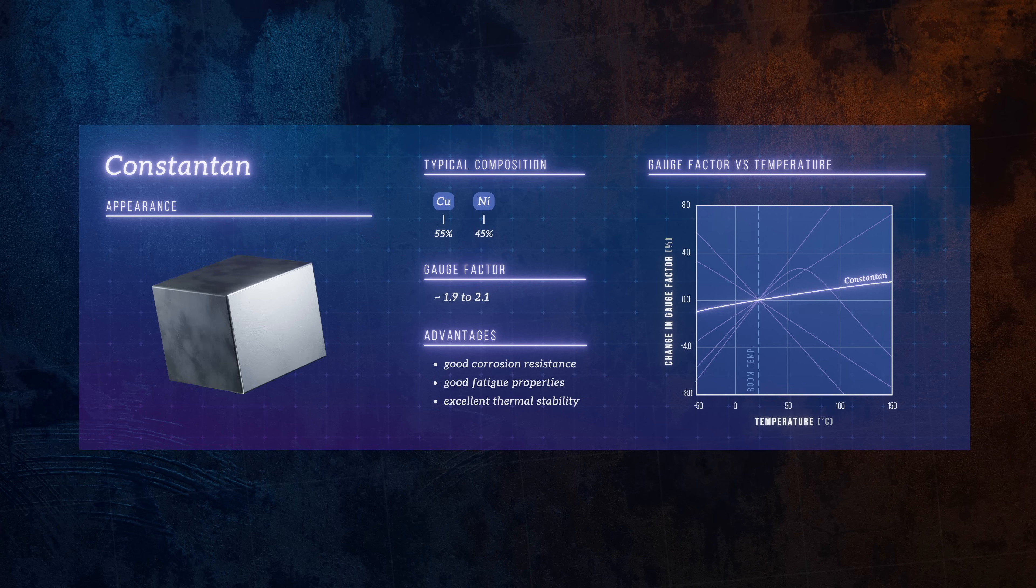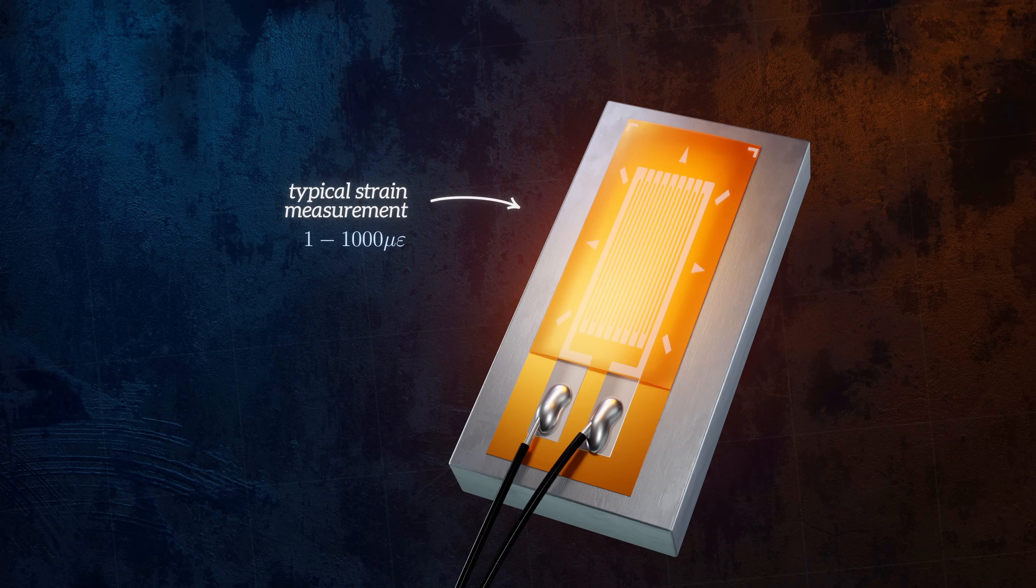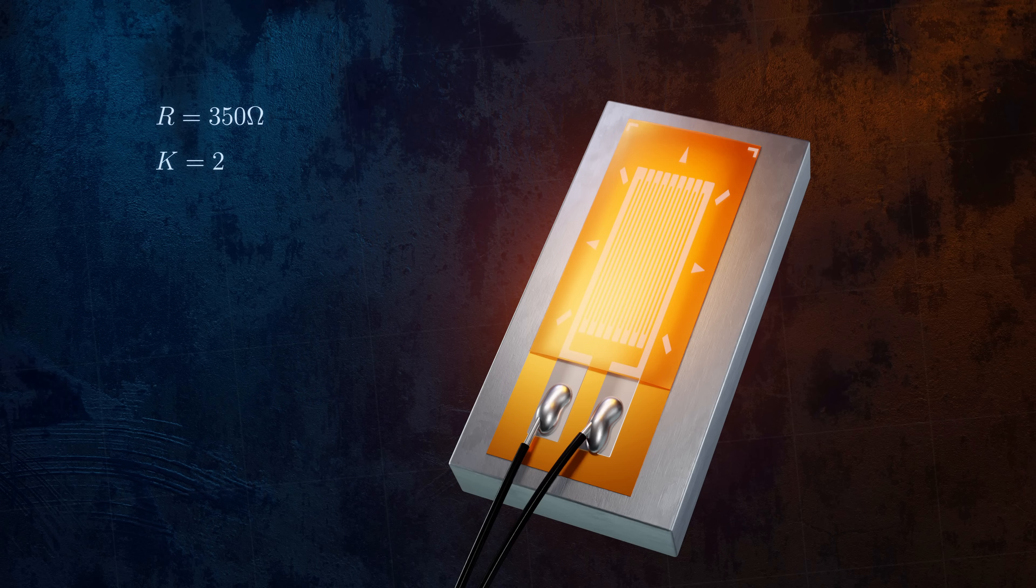Strain gauges are usually used to obtain precise measurements of small strains, typically in the order of 1 to 1000 microstrain. A standard unloaded Constantan strain gauge has a resistance of 120 or 350 ohms. Assuming a resistance of 350 ohms and a gauge factor of 2, a tensile strain of 100 microstrain will result in a 0.07 ohm increase in the resistance of the strain gauge.